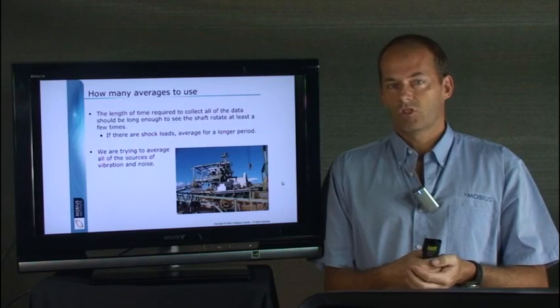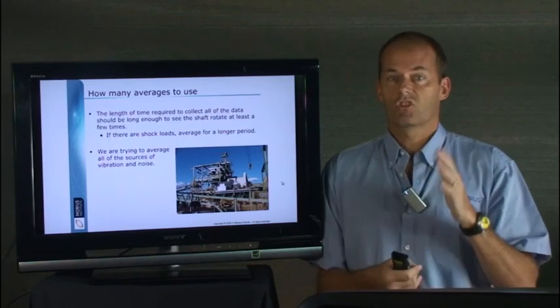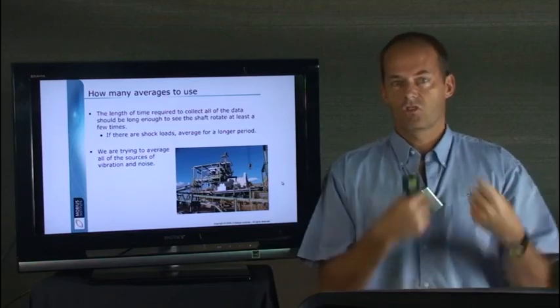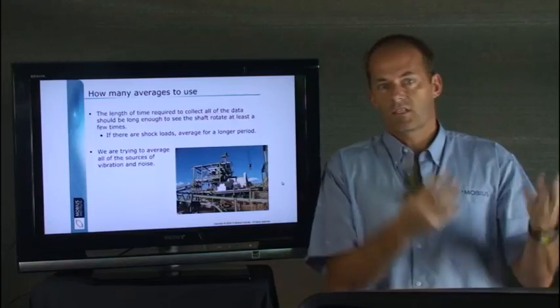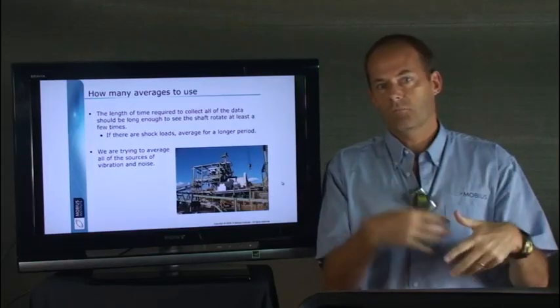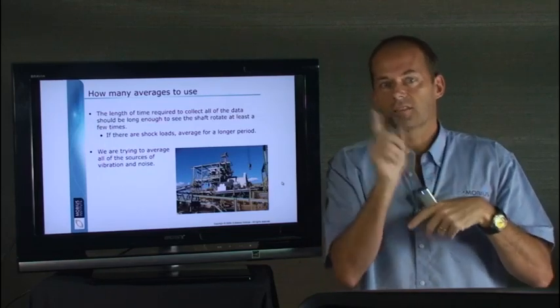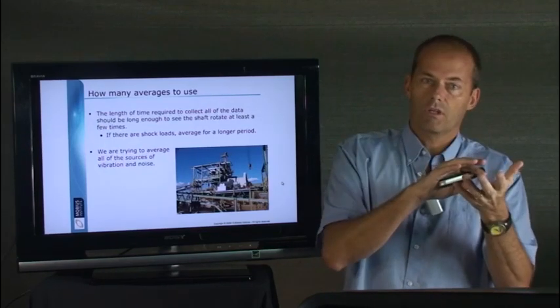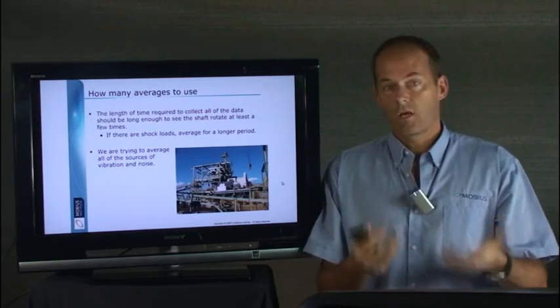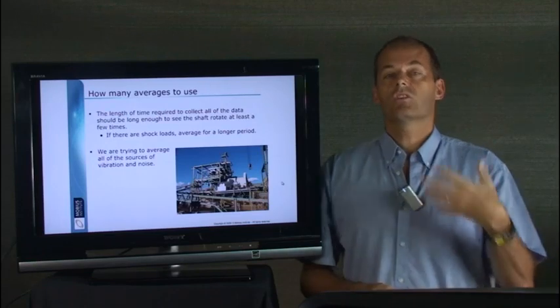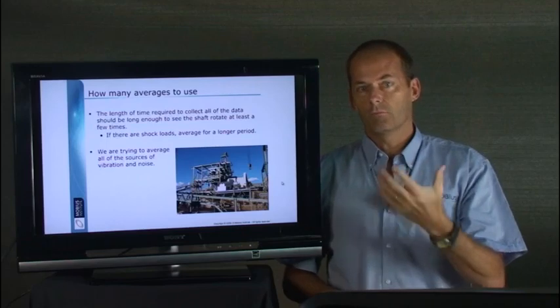What you've got to visualize inside a machine is that from one moment to the next the vibration does change because the shaft is turning, liquids are flowing through the pump, the gears are meshing together and it can take time for certain gears to come into mesh with other gears, the balls are rolling around in the bearing and they're spinning and any damage on the balls will come into contact with the outer race sometimes and inner race. There's just all sorts of things going on inside your machine and you just have to make sure that you're listening to it long enough to get that full message.